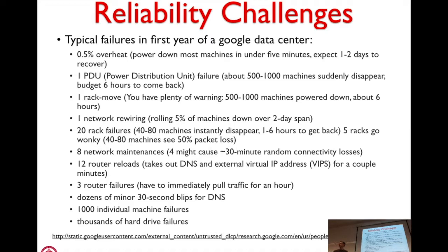Some examples of different things that can fail: overheating, where some percentage of machines overheat due to imbalances in the cooling infrastructure. One PDU failure for about every 500 to 1,000 machines, a PDU being a power distribution unit, basically an industry-scale power strip, a huge thing that's just a bunch of plugs. You might also have to move racks, which causes a bunch of machines to be powered down.